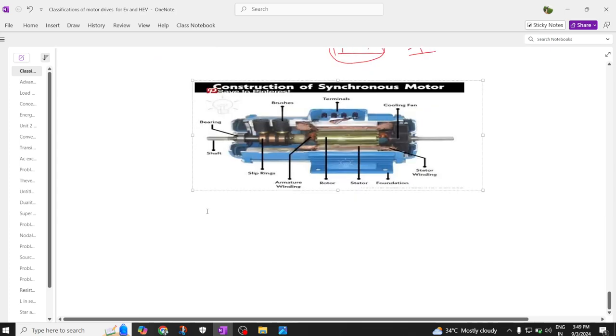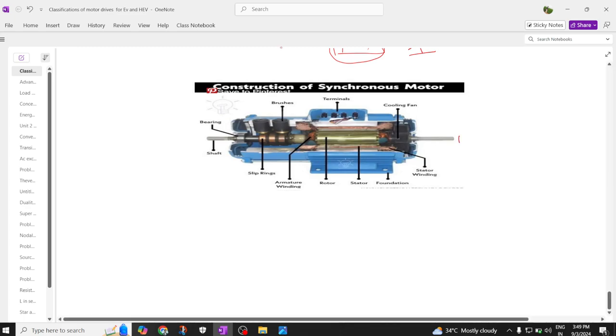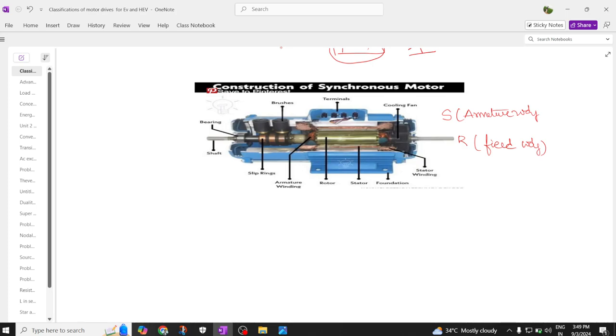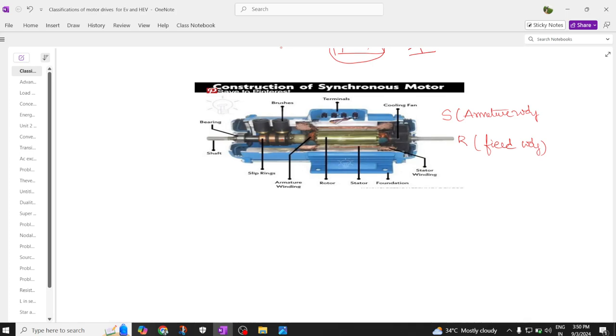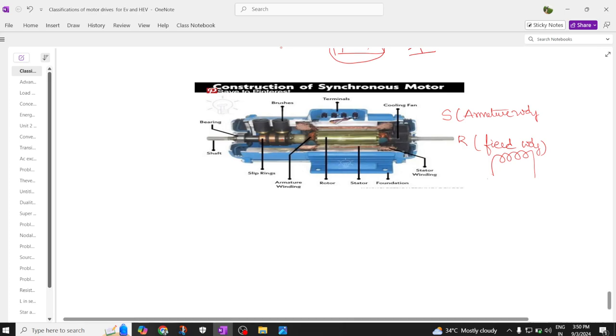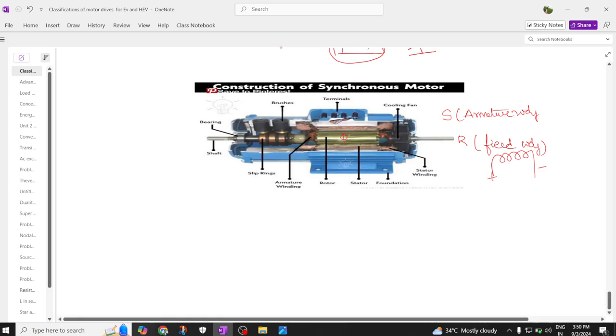In the synchronous motor, coming to the construction — already I told this synchronous motor has two parts. This part is called the rotor part and this part is called the stator part. To this rotor part, you have the field winding, and the stator part has the armature winding. This is the rotor, and all these windings are wound and brought out across the slip rings. These are the three slip rings, and carbon brushes are attached to the slip rings — because to excite the field winding, we give the supply through the carbon brushes, it comes to the slip ring, goes into the field winding, this acts like an electromagnet, and flux is produced.